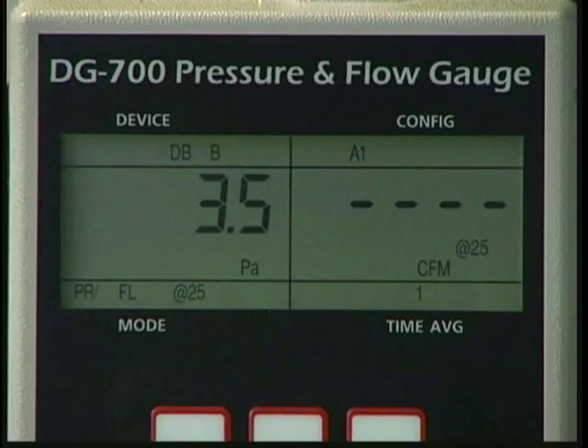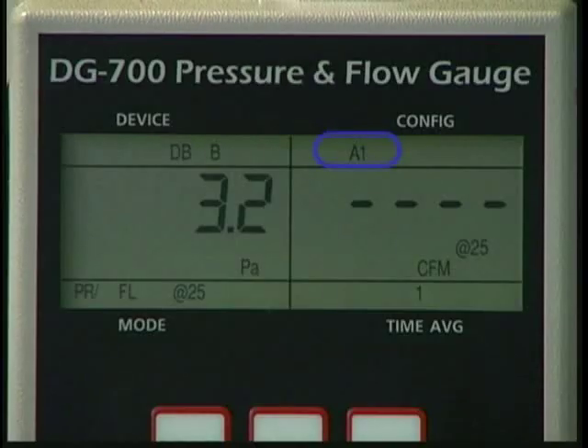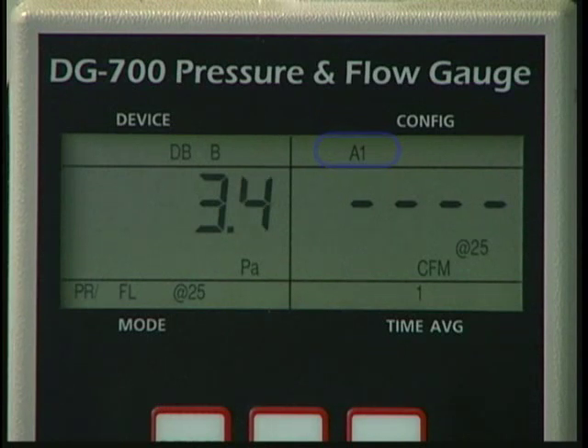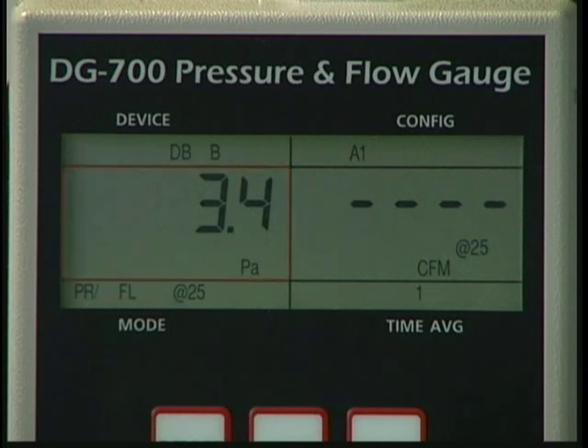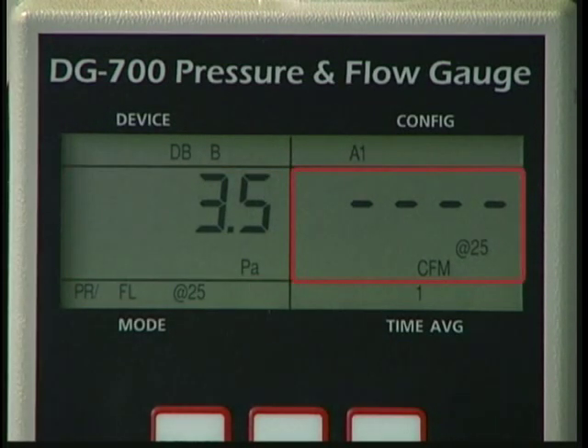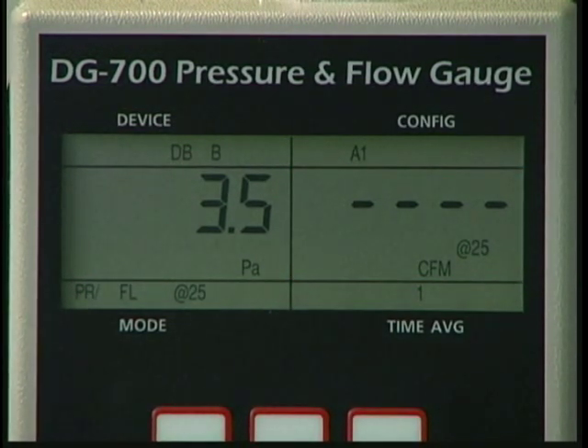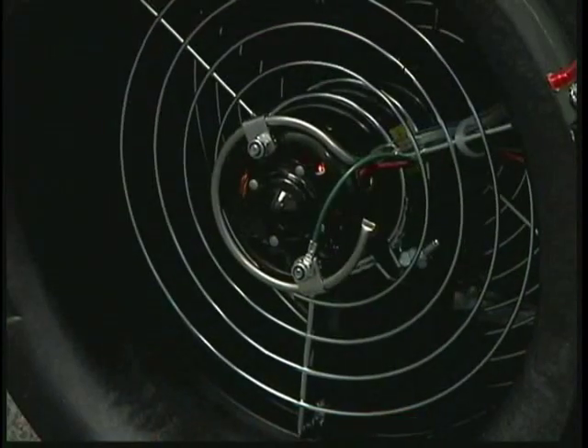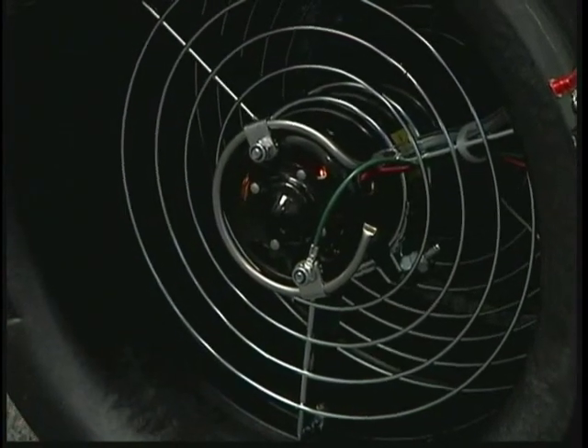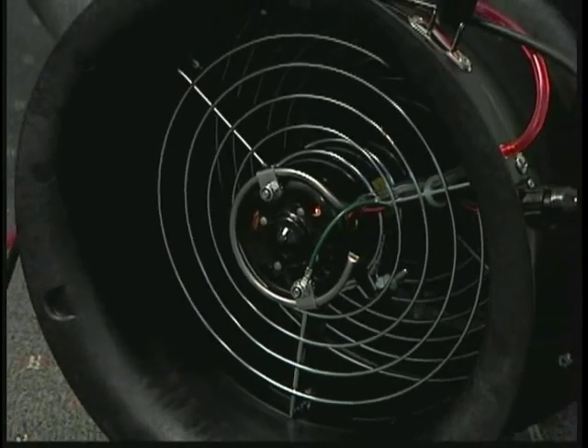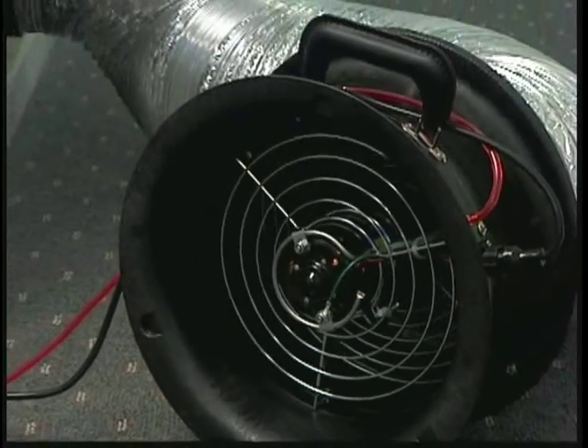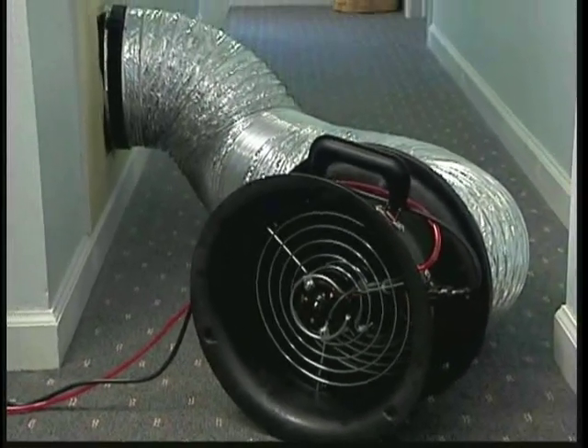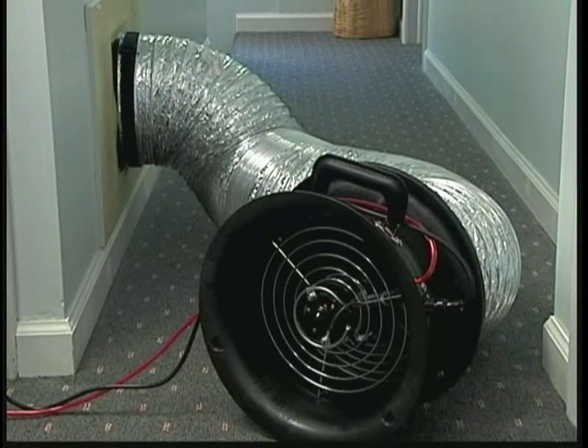Now let's look at a different example of how the gauge signals you to change flow rings. Suppose you have installed ring 1 on the fan, and even though the Duct Blaster fan is running at full speed, you are not able to achieve at least 5 pascals of duct pressure on channel A. In this case, the gauge will display a dashed line on channel B, indicating that you should install a larger flow ring or remove the flow rings entirely to generate more fan flow. In this example, the operator should try conducting the test with no flow rings installed rather than ring 1 in order to generate more fan flow and increase the test pressure.